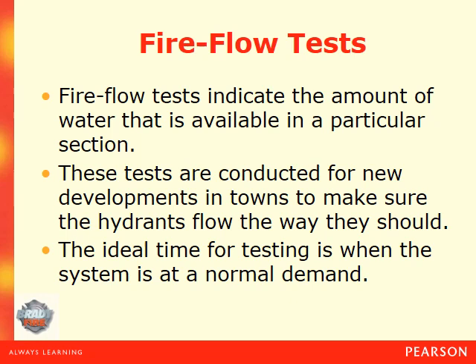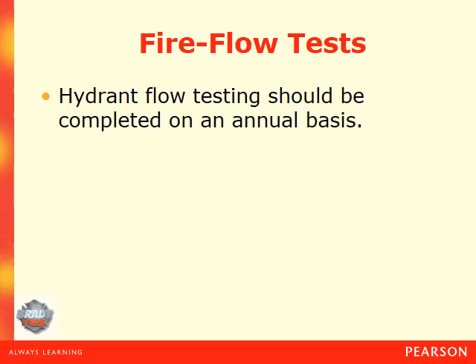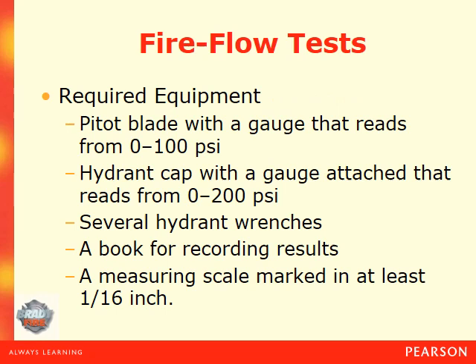A fire flow test indicates the amount of water available in a particular section of the water system. Tests are conducted for new developments in towns to make sure hydrants flow as they should. The ideal time for testing is when the system is at normal demand, and annual testing should be done on hydrants. You will need the following equipment: a pitot blade with a gauge reading 0 to 100 PSI, a hydrant cap with a gauge reading 0 to 200 PSI, several hydrant wrenches, and equipment to record results.